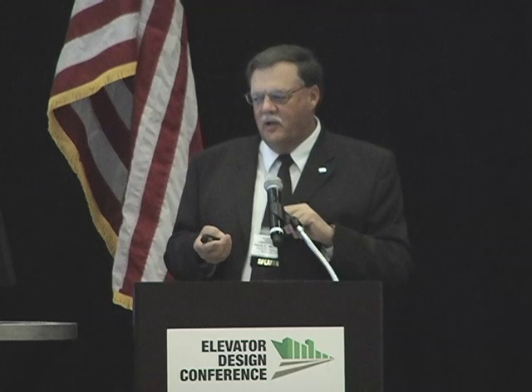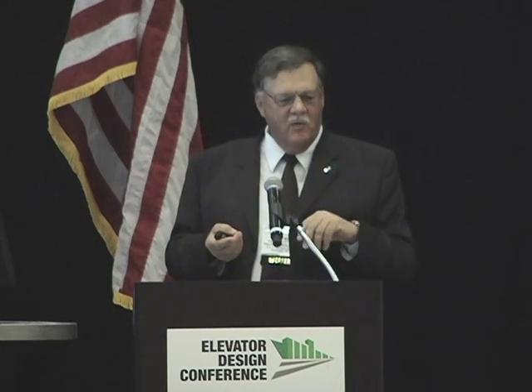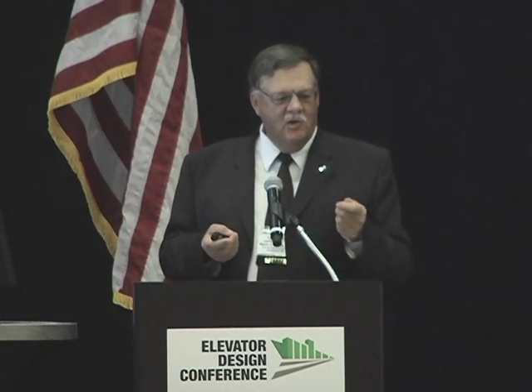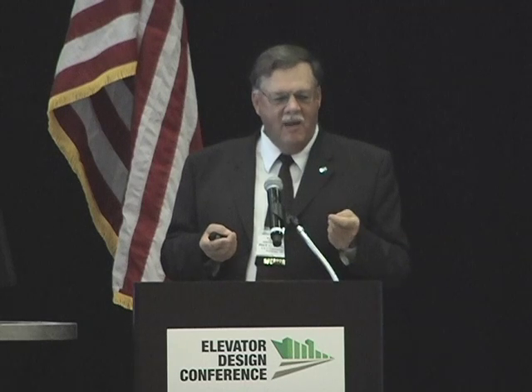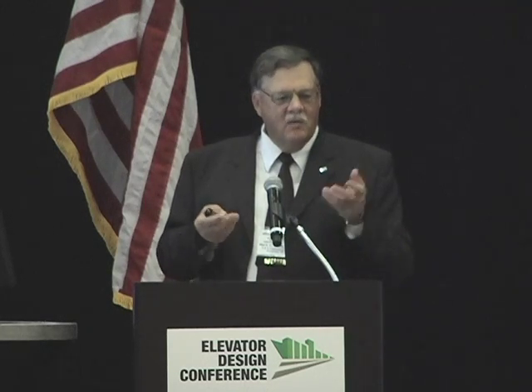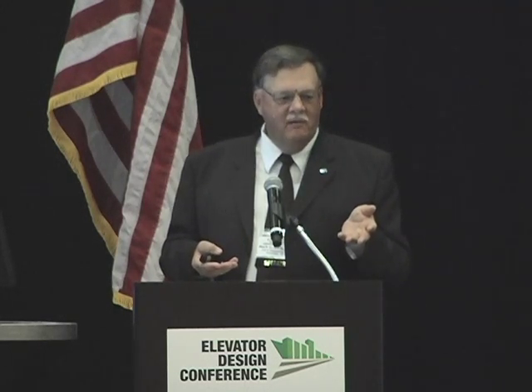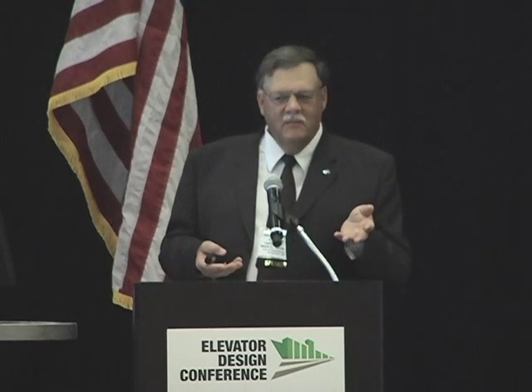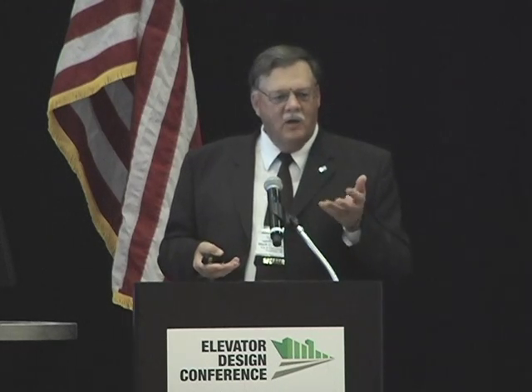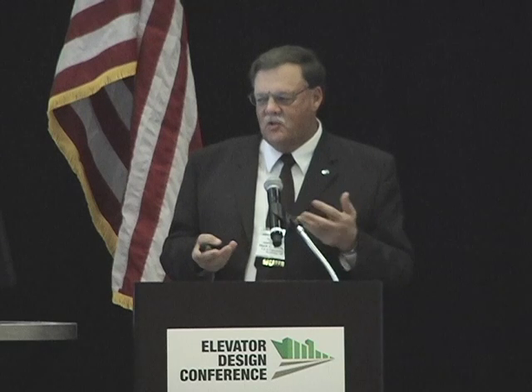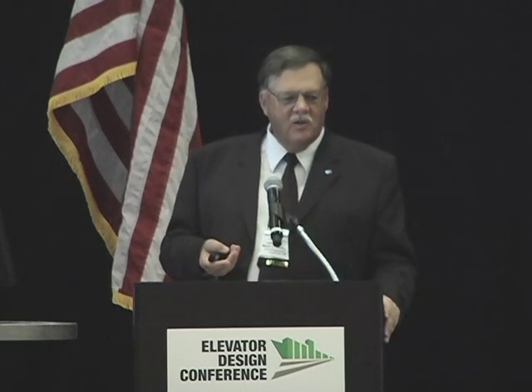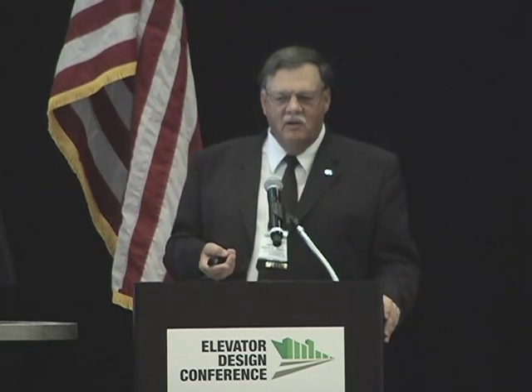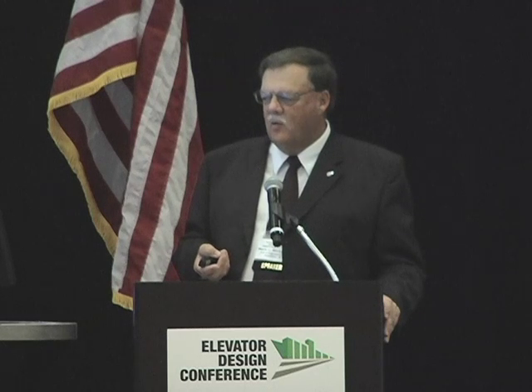And he can flip a switch, and the tripping characteristic of the breaker changes to another setting automatically that's been configured to reduce his PPE requirement on the arc flash level. So we actually have breakers with multiple tripping characteristics, so you can switch it into a maintenance mode and reduce your arc flash and safety requirements.